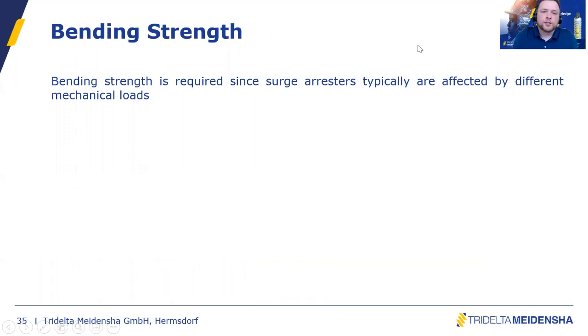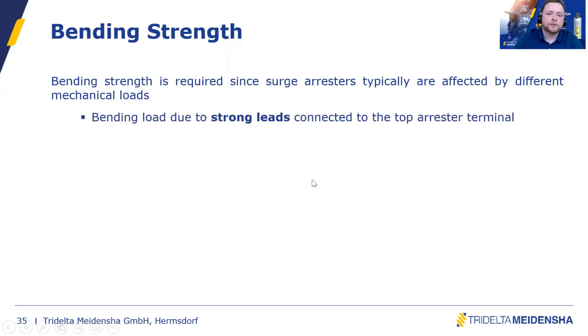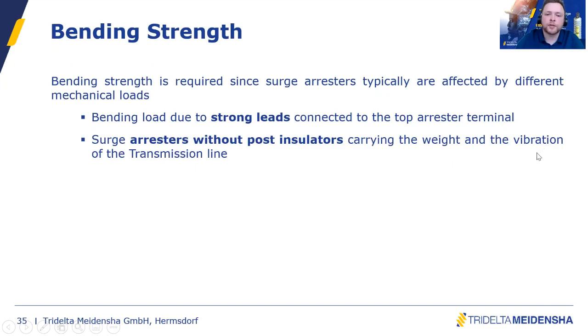One other property of the surge arrestor we always have to consider when we select or design a surge arrestor is its bending strength. Bending strength is required because those surge arrestors are typically affected by mechanical loads. We have strong leads that are bent down to the surge arrestor, which provide a static force to the surge arrestor. We have surge arrestors which are not equipped with post insulators in the direction of the line. So the line itself has a direct influence on the mechanics of the surge arrestor by its weight and by the vibration of the transmission line due to wind loads and, yes, short circuit current.